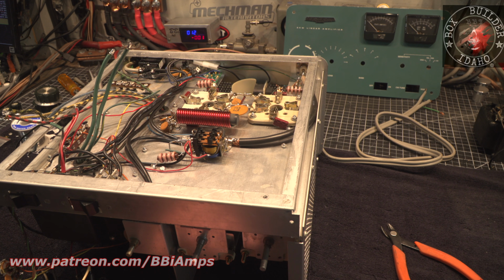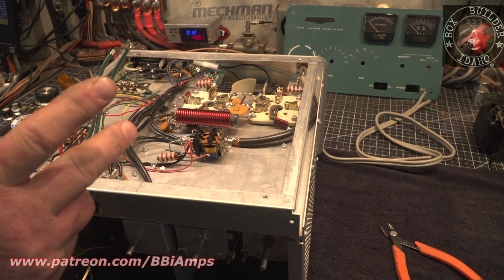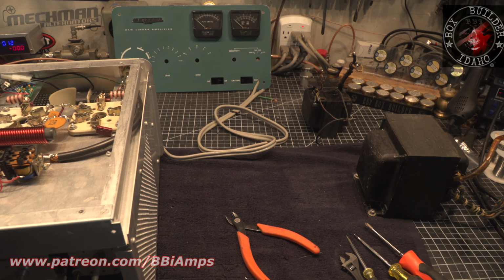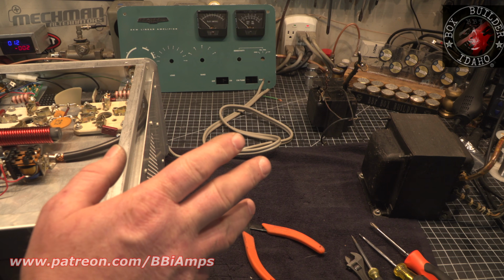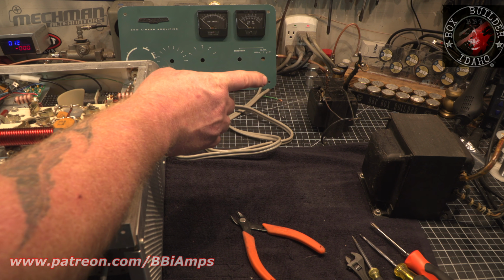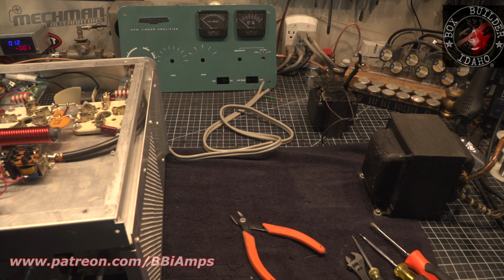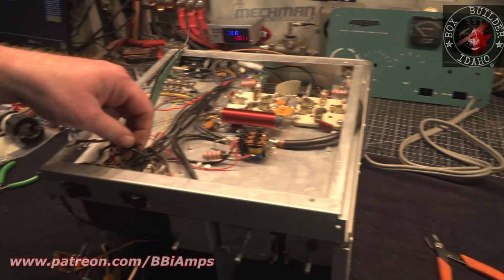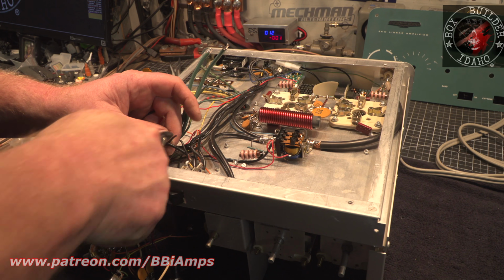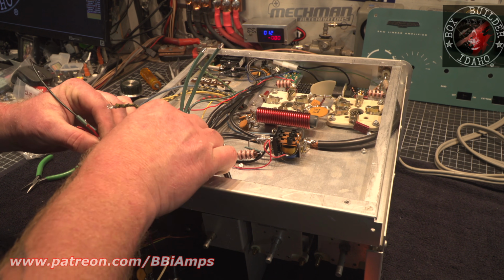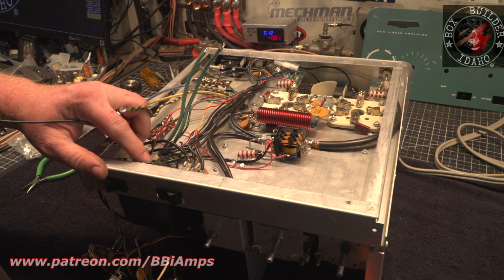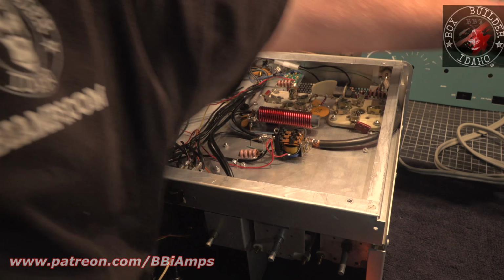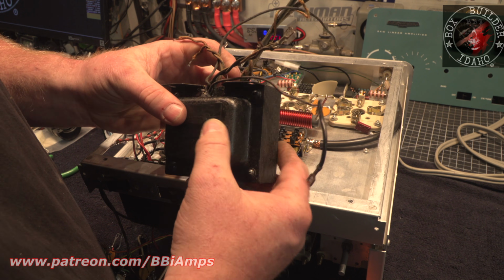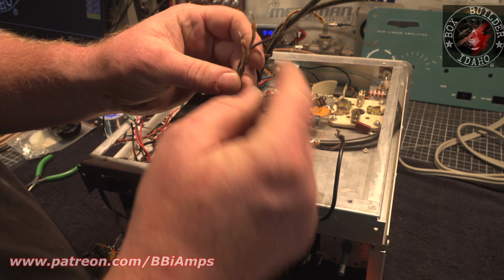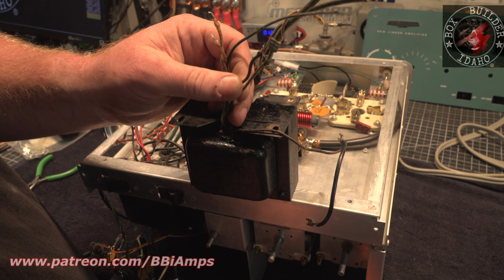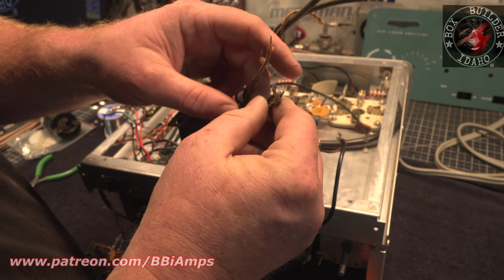But everything's disconnected now. Now you guys know with the older transformers over here, the color code's the same but slightly different, I guess would be the best way to put it. The colors over here are really faded, so we really have to pay attention to where things go. So this black and red translates to this black and red. So I'm just going to go ahead and cut that. It's like this black and yellow here translates to this black and yellow, but then the black and yellow on this filament transformer, which is what? Should be two reds, a green and black, black and yellow. I'm assuming this is our black and yellow.